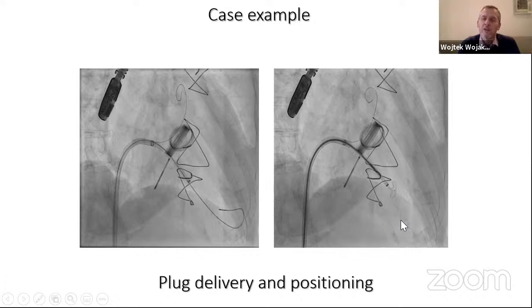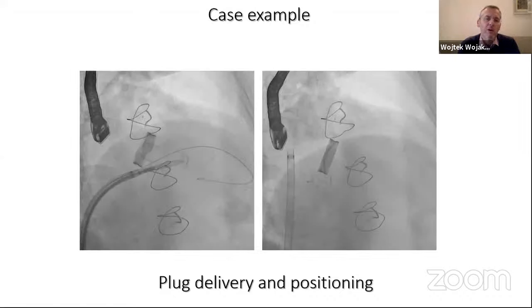This is an example of the PLD device being deployed. It's being pulled, and the safety wire in the atrium provides some distance. And also for this type of device, it's very important to have the echocardiographer, who will precisely tell you when the ventricular portion of the device is properly located. And so the opening of the atrial portion is guided by the position of the ventricular portion on the other side, confirmed by the echo. So this example showed that you can have your plug open, being withdrawn, and at the same time you can keep your safety wire in the atrium to guide you back once you lose your position. And this is the plug which is deployed.